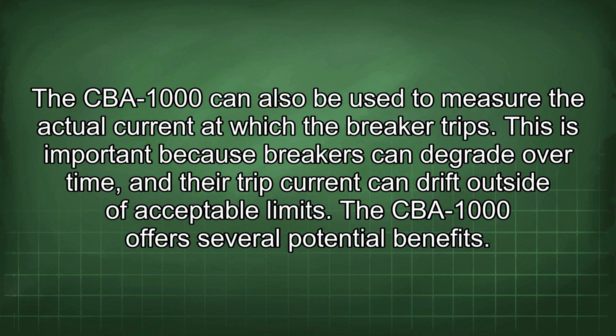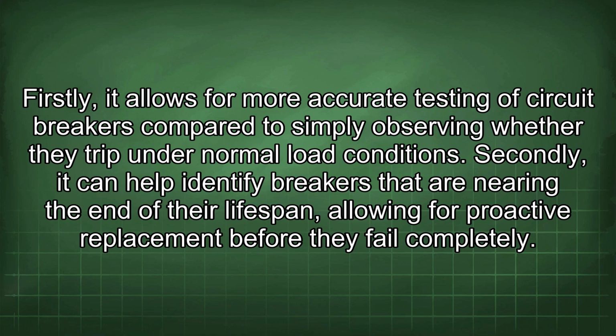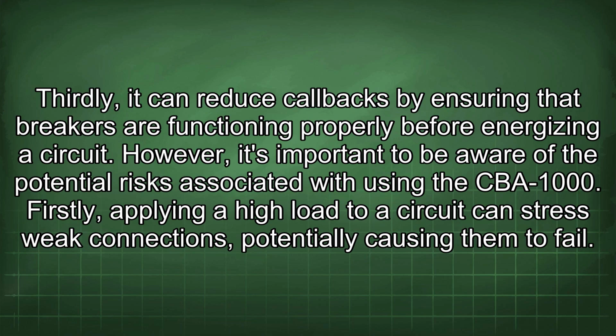The CBA-1000 offers several potential benefits. Firstly, it allows for more accurate testing of circuit breakers compared to simply observing whether they trip under normal load conditions. Secondly, it can help identify breakers that are nearing the end of their lifespan, allowing for proactive replacement before they fail completely. Thirdly, it can reduce callbacks by ensuring that breakers are functioning properly before energizing a circuit.